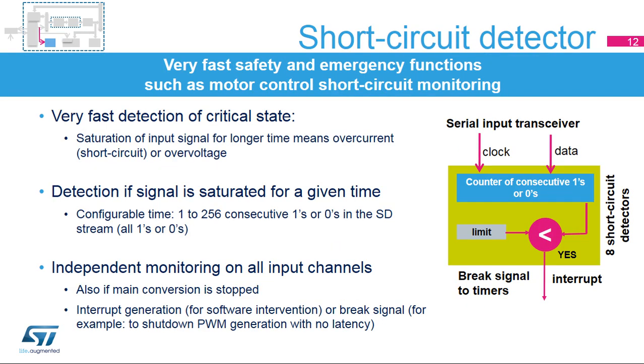The short circuit detector monitors input serial channels for a saturation state. When an input signal is saturated, it is outside the allowed measurement range, indicating overflow or underflow. When measuring current, this typically detects an overcurrent or short circuit; when measuring voltage, it detects overvoltage. Detection is based on monitoring the input serial data stream and watching for a consecutive set of ones or zeros over a relatively long time. This maximum saturated time can be set from 1 to 256 sampled input data with the same value.